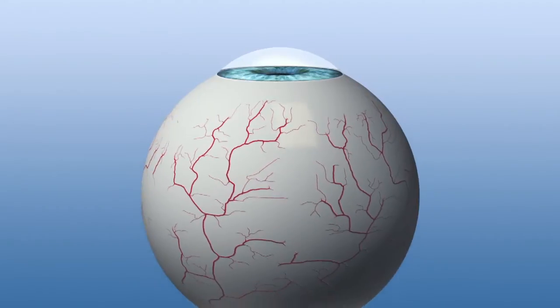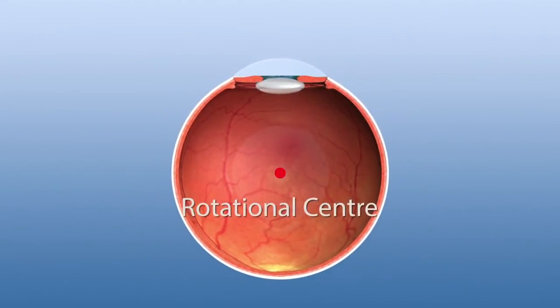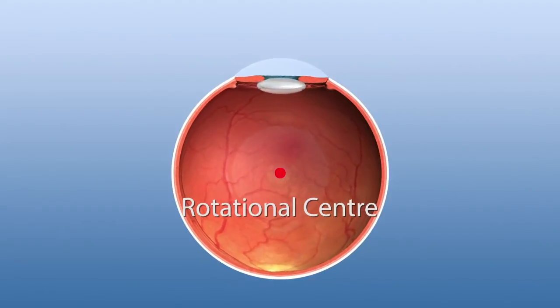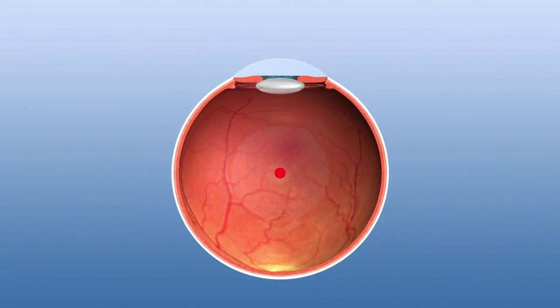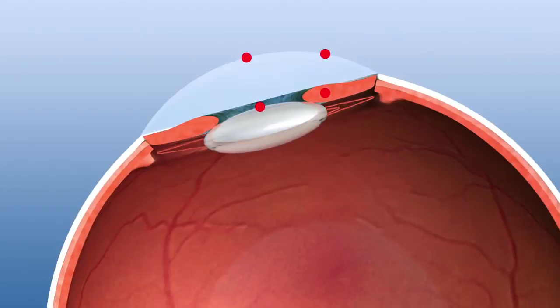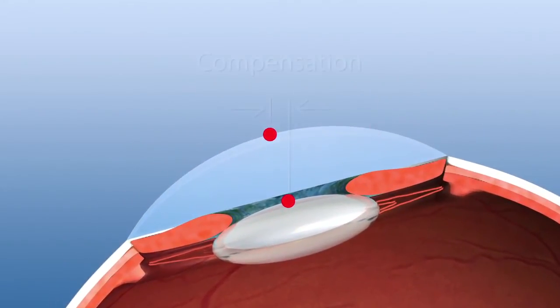In surgical practice, the cornea rolls along the eyeball's rotational center about 13 mm below the cornea. This causes a displacement between the pupil's center and the intended ablation center. The Schwind Amaris eye tracker balances all those eye rolling displacements.